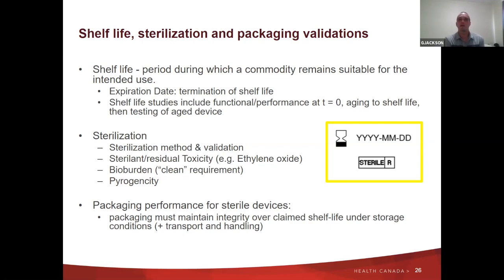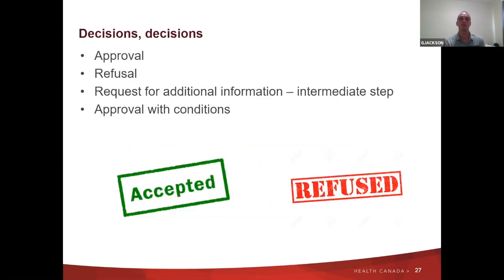And so we need to look at whether their packaging can survive shipping and maintain sterility, and then whether the sterilization can actually sterilize the full device, because some are designed in a complicated way. So you need to make sure that the sterilization they're using will actually get all the parts of the device that need to be sterilized. And more so for class four devices, these are even required.